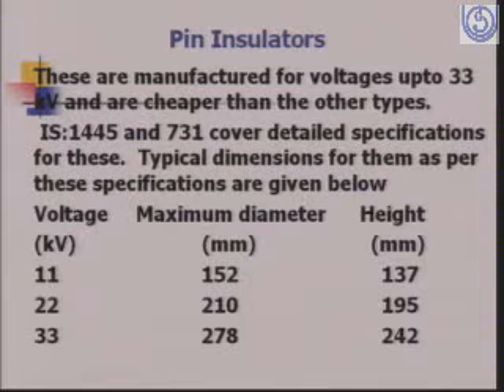Then we have the pin insulators, most commonly used. These are manufactured for voltages up to 33 kV and are cheaper than the other types. IS 1445 and 731 cover the detailed specifications for these insulators, and their typical dimensions are as indicated in the slide. For 11 kV, maximum diameter is 152 mm and height is 137 mm. For 22 kV, the maximum diameter is 210 mm and height is 195 mm. Then 33 kV, the maximum diameter is 278 mm and the height is 242 mm.